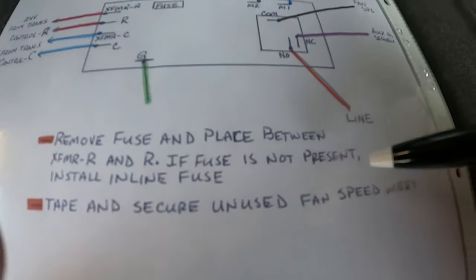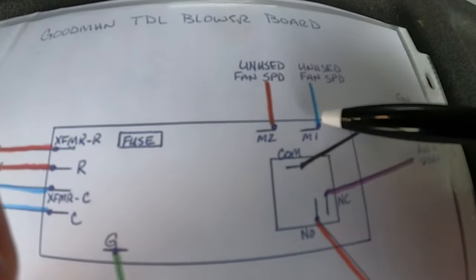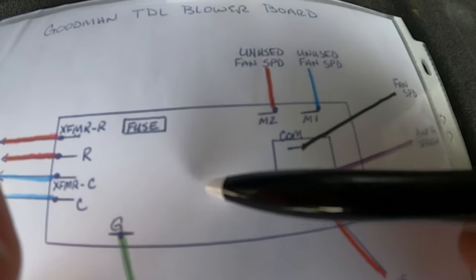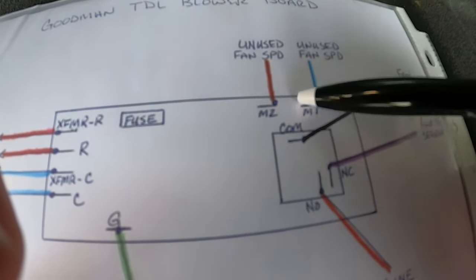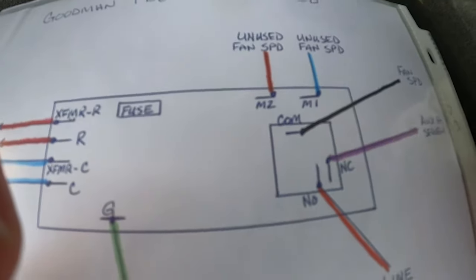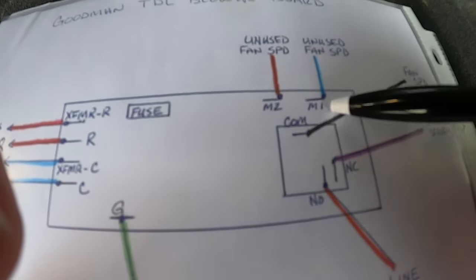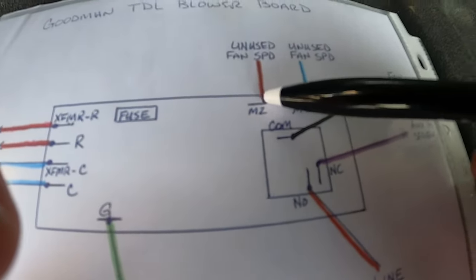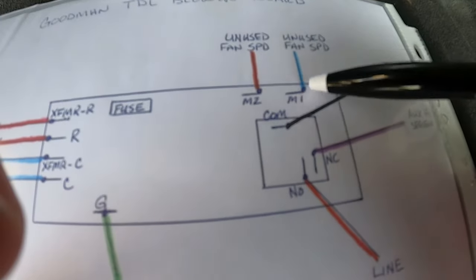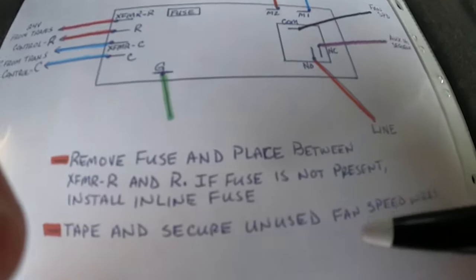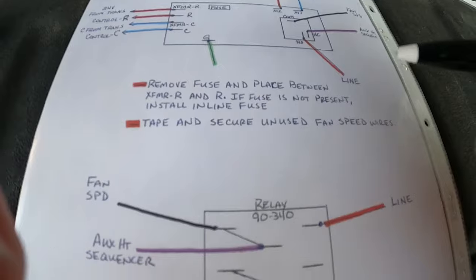Your unused fan speeds, which are here and here, if the board's not that badly damaged, you can leave them plugged to it and just leave the board in it. Or you can take these off, cut the stake-ons off the end of each one, and put a wire nut on each one. And that tells you how to handle your unused speed wires.